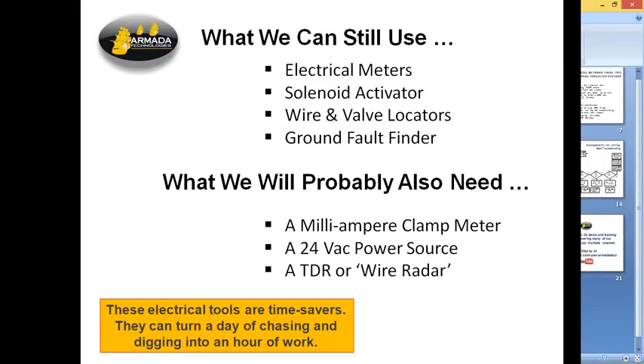24-volt power source. Now, what you'll also hear from the two-wire vendors, and it's an excellent idea, is to have a power source there so you can power the field wire up separately from the controller. You're disconnecting from the controller anyway to do locating, to do some resistance checks, but if you want to get out there and start feeding some current and voltage down the wire to help isolate problems, putting your own 24-volt power supply on the line is a good idea. And you can get these things for less than 20 bucks. We've got a picture of one later. Lets you do troubleshooting independently from the controller, because if the system's kind of gone really flaky, the controller will let go anyway and it won't supply power, and you have to have power on the cable to troubleshoot.